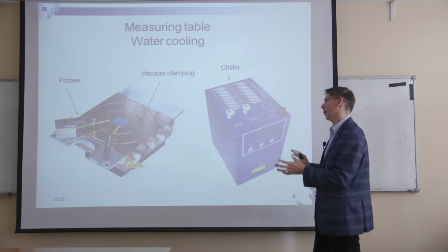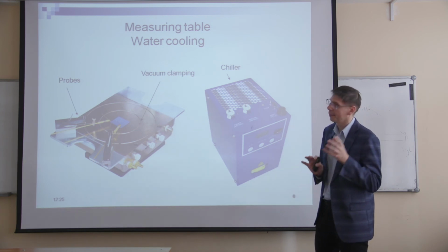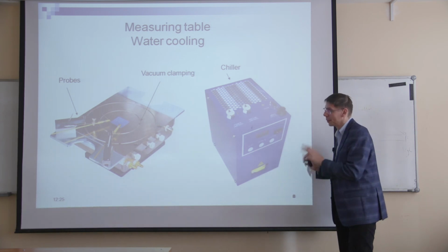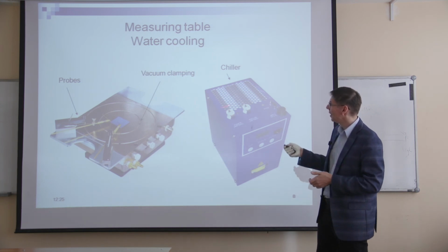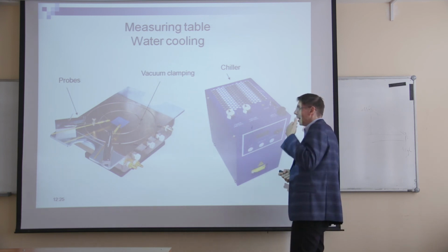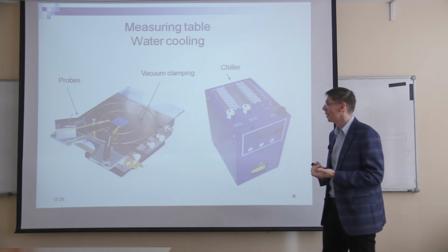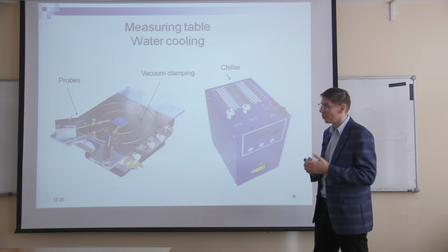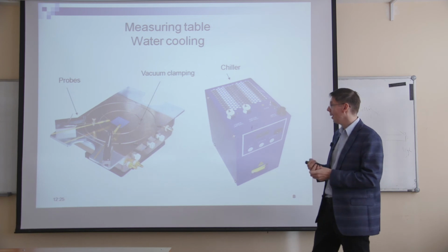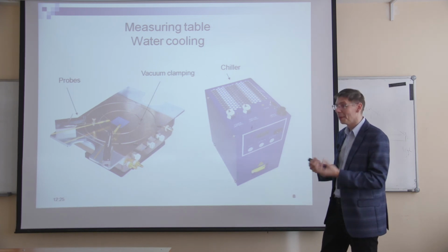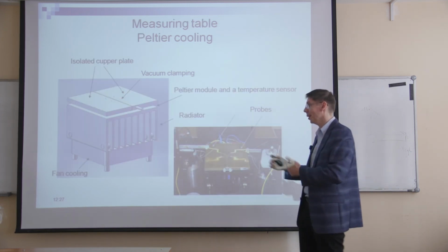I mean, if you are thinking only about the standard condition at 25 degrees, it's not so bad. Disadvantage is that, with any liquid cooling system, unfortunately you have a chance of a leakage. If you have some water or any other liquid and you have a leakage, it's not really nice for your devices.